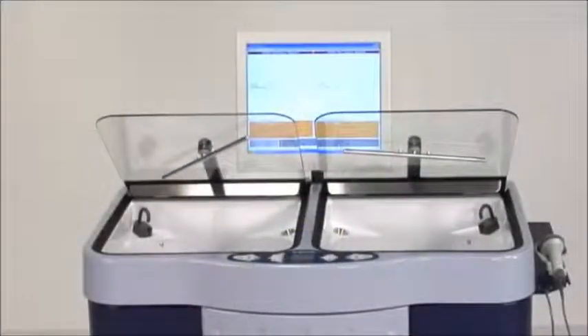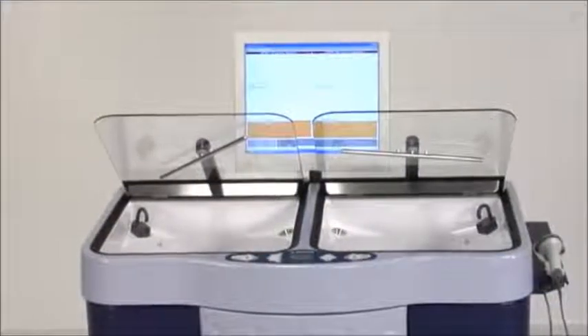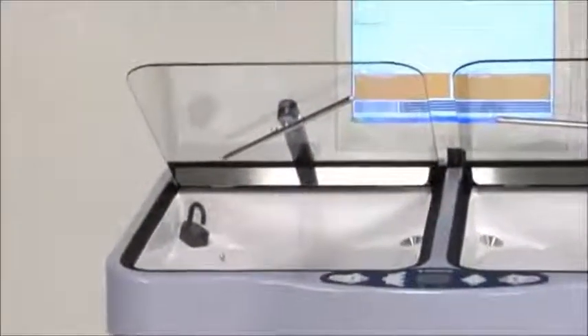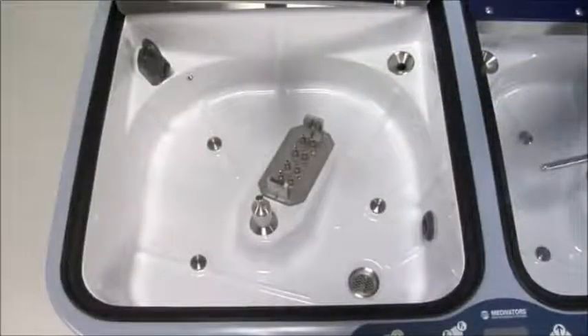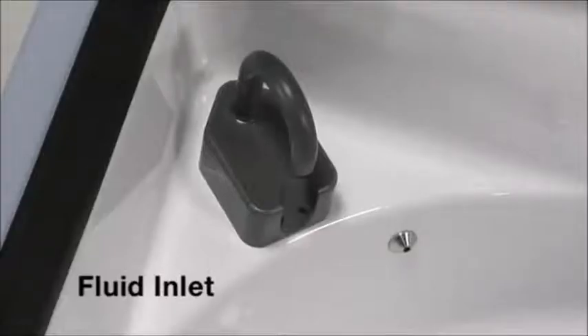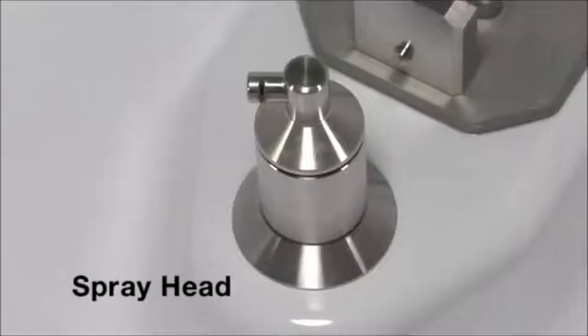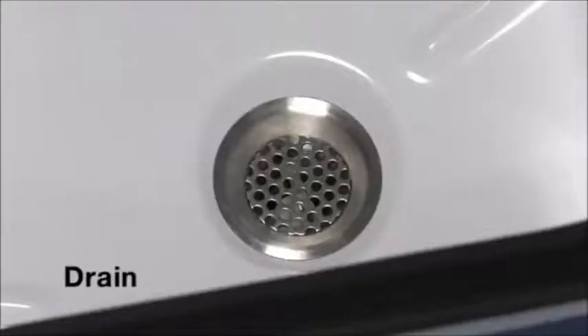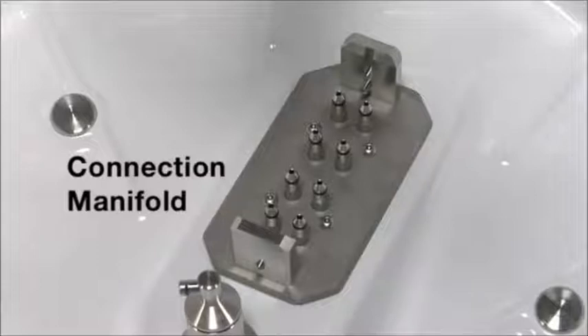The Advantage Plus functions as two disinfectors in one. Each basin operates independently. The following components are inside each basin. The fluid inlet dispenses water and Rapicide PA Part A and Part B. The spray head disperses a fine jet of fluid throughout the basin. The overflow outlet drains excess fluids. The drain discards waste fluids. The connection manifold attaches the endoscope hookup blocks to the monitoring system. The connection manifold dispenses fluids and air through the channels of the endoscope.